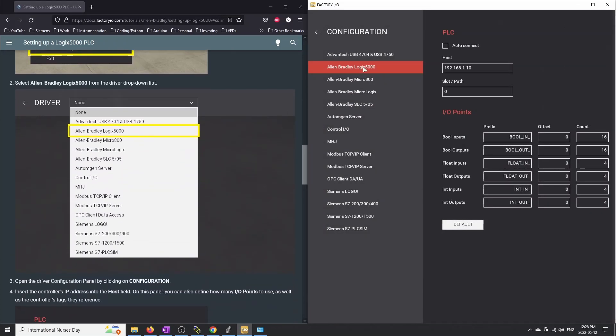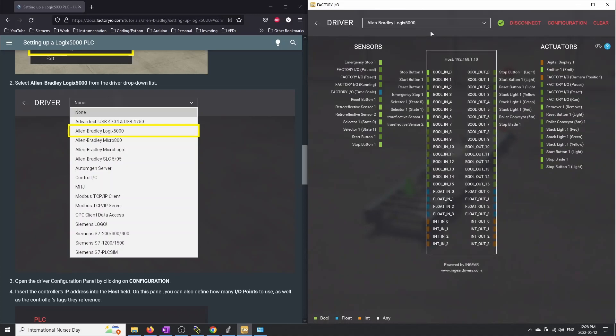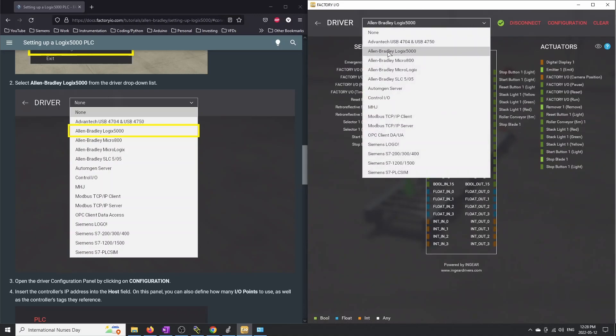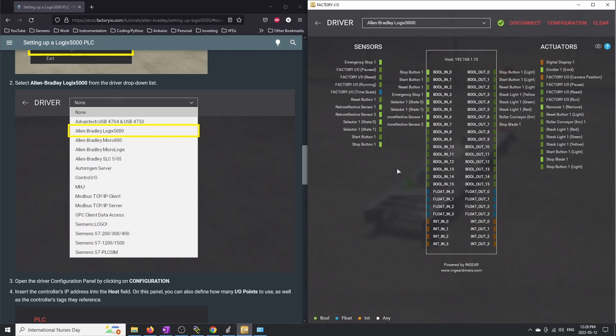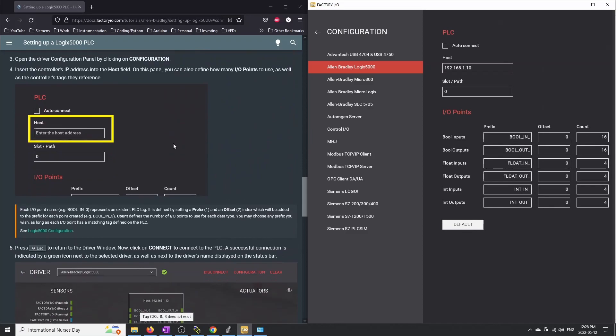You can see it's already set up with a specific environment that has a control panel, a conveyor, and a couple of sensors on the conveyor belt. From here, go to File, then Drivers, then Configuration. You're going to choose Allen Bradley Logix 5000. If that's not already shown, click and select Allen Bradley Logix 5000 from the list. Once you've done that, go to Configuration and put in the specific IP address for your PLC.